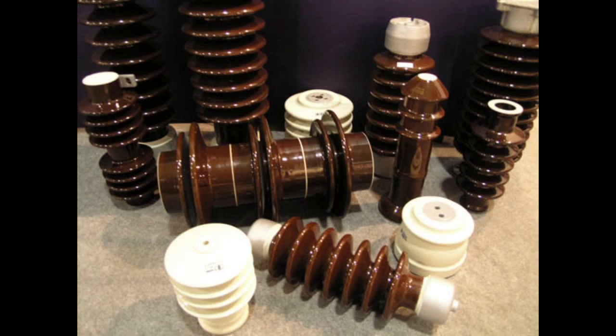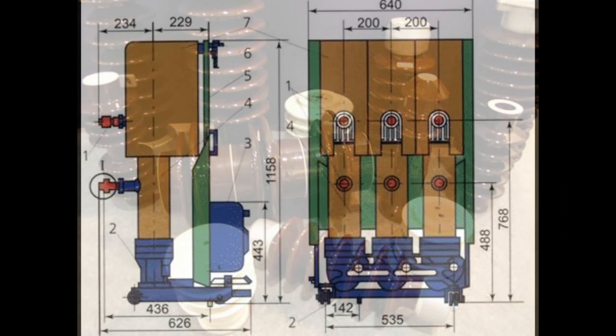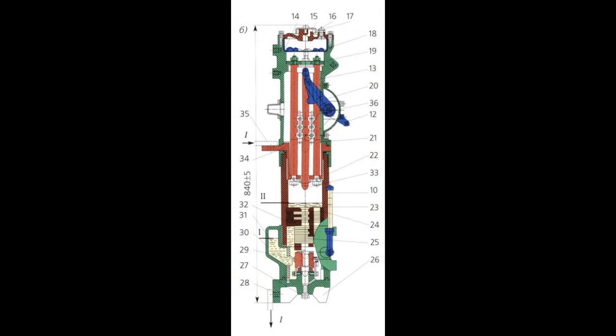Low oil content circuit breakers use highly insulating materials such as ceramics to ensure insulation and arc suppression from the ground. Oil is used only to produce gas. Each break in the circuit has a separate chamber with the arc suppressing device. When in the diverged position, the movable contact is situated above the oil level.